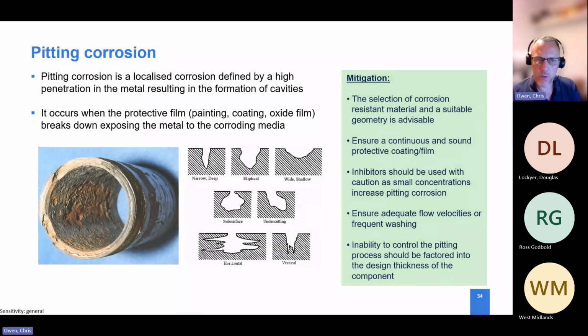Pitting, so going back to the thin wall tube, pitting occurred because we saw rapid acceleration in a very localized place. Pitting is normally a result of something which has happened on the surface of the tube - either there's a defect there or a localized breakdown. It could be that pitting takes place because of another corrosion reaction called MIC, microbiologically induced corrosion, where debris or biofilms build up on the internal surface of the tube.